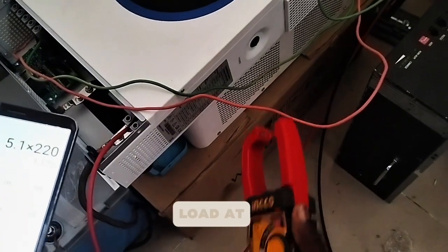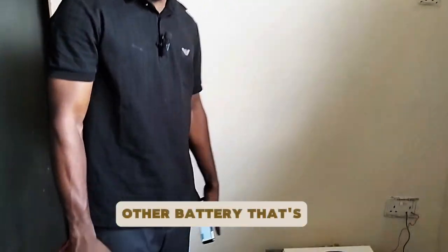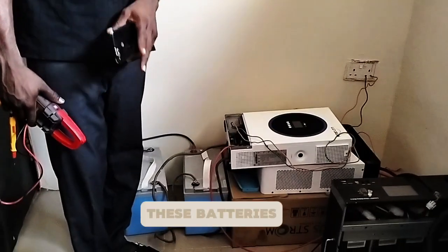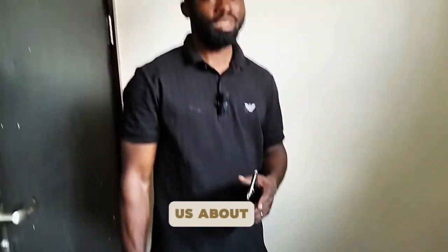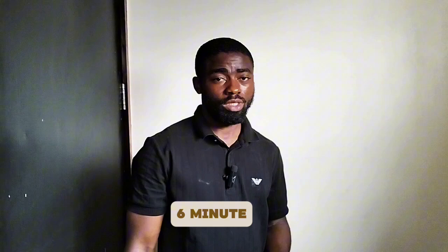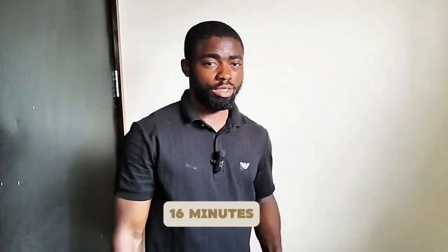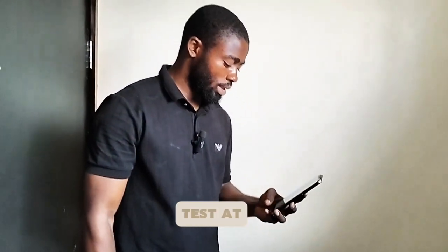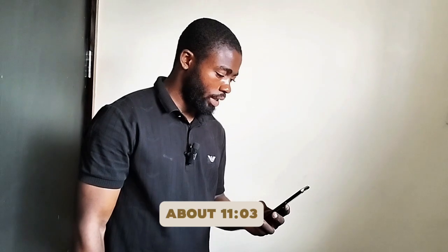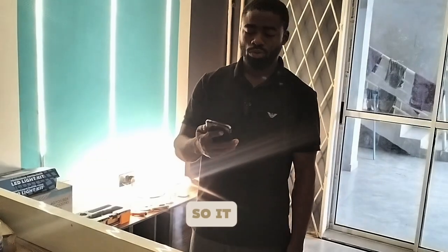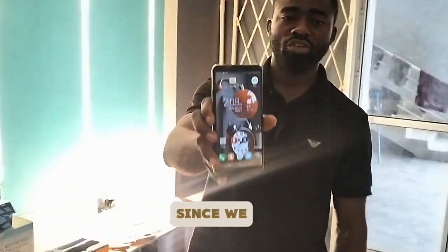With this amount of load at 80% DOD, if this other battery that is on 13.4 doesn't go off, these batteries are expected to give us about 3 hours 6 minutes or 3 hours 16 minutes. So we started the test at about 11:03 and this is about 2:08. So it's been 3 hours 5 minutes since we started this test.